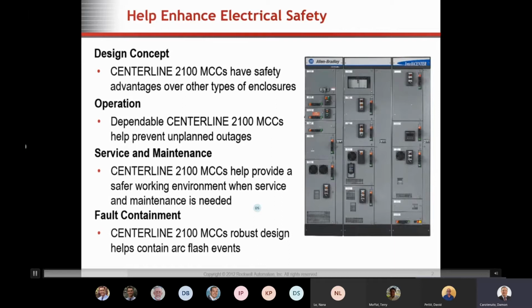Another nice thing about the Allen Bradley MCC is by design it's inherently safe due to fault containment. It's structured with top and bottom plates on each bucket, as well as heavy-duty hinges on the door. We have dual side plates, we don't share a single side plate. So just by the design of how this is manufactured, as the standard, without any options, it's a relatively robust MCC, trying to maintain any arc flash events by containment and hopefully stopping them from cascading into other units.